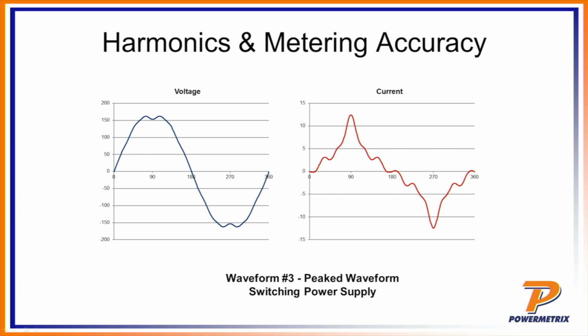Saved me energy because the total watts being consumed by that refrigerator went way down, but it generated a lot more harmonic energy, meaning that there were more VARs and more harmonics that the utility was paying for that were not being caught by the watt-hour meter. And so once again, that's a loss for the utility.